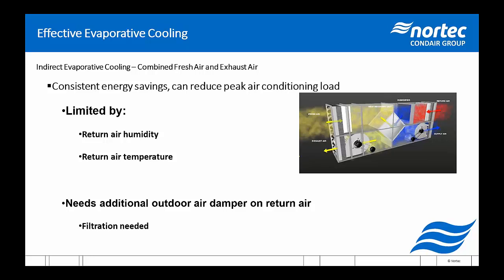We can see some fairly significant energy savings, and with rebates, we're talking 1 to 2 year payback periods in replacing a lot of electric humidification or even gas steam humidification. And when we look at evaporative cooling on its own, we're potentially using a less expensive system, which allows us again to see 1 to 3 year payback periods, depending on the setup and the location and the building economizer and how much fresh air. And I could go on. There's lots of depends. But that being said, there's always a good reason to look into it.